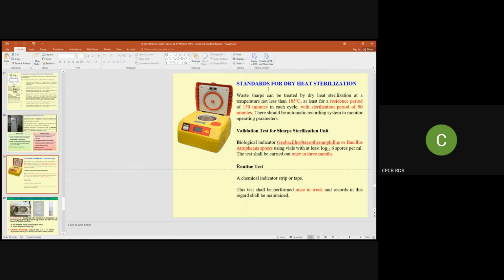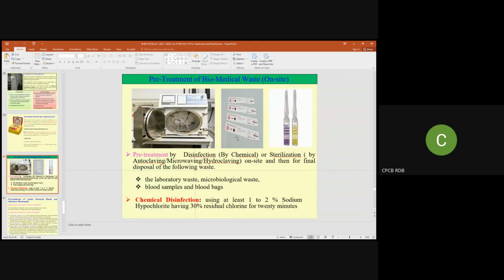Generally, this technology can be used for waste sharps only. Only waste sharps can be treated using this technology. And generally, the test conducted for achieving the efficacy of this particular technology uses a biological indicator of Geobacillus stearothermophilus or Bacillus atrophaeus spores, to assess whether the technology has achieved log 6 efficacy or not. This test has to be conducted once in 3 months, and a record has to be maintained. The routine test is once a week. The test has to be conducted using these strips or tapes. It is a simple technique you all might be knowing. Of course, in the last class I told about these spores.